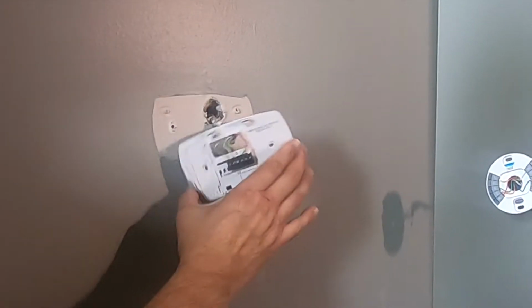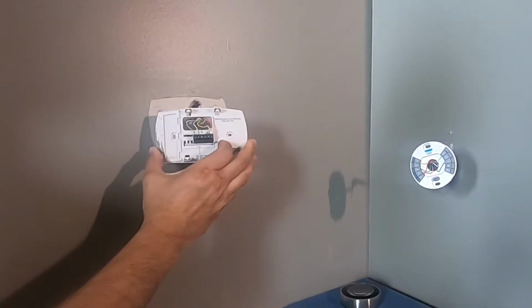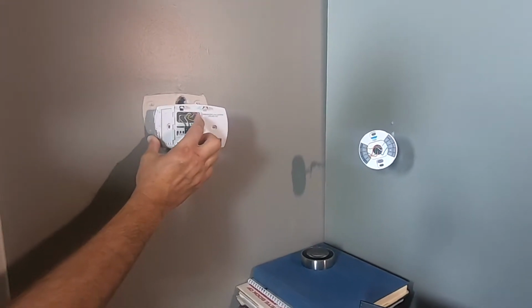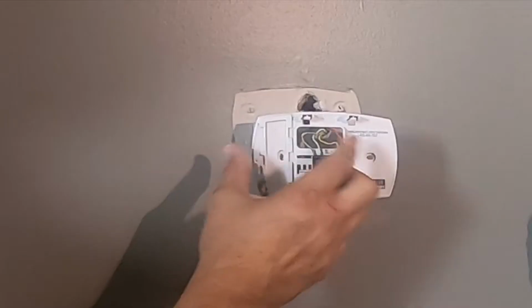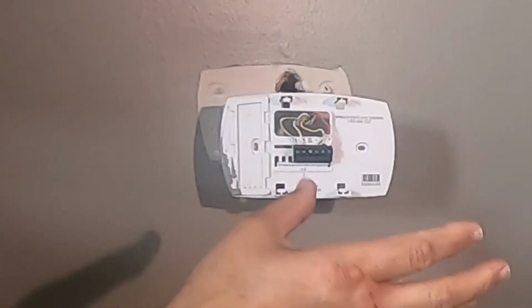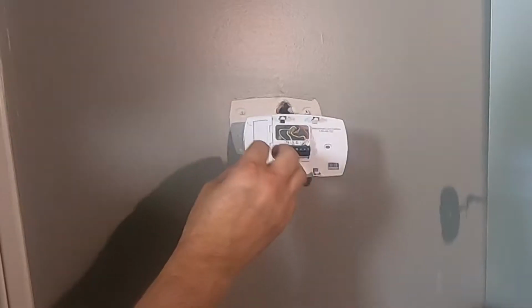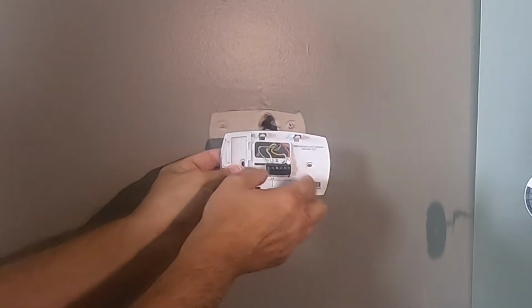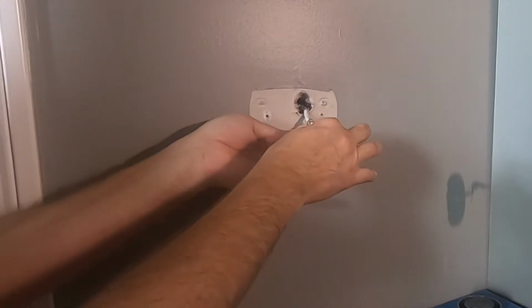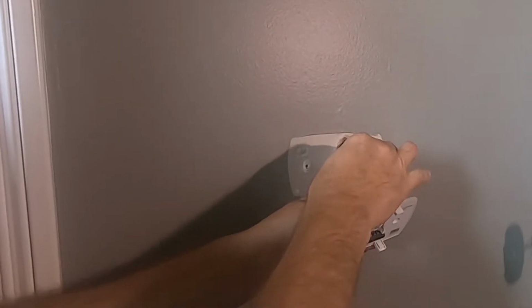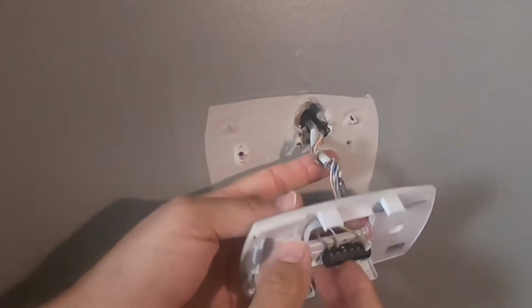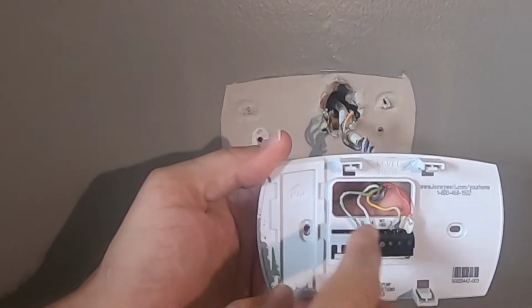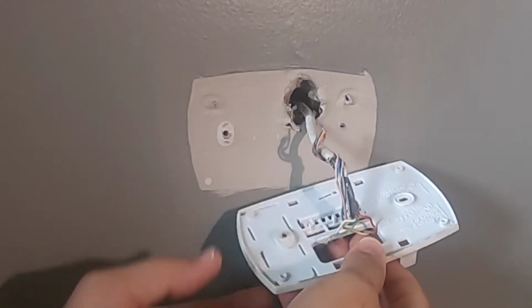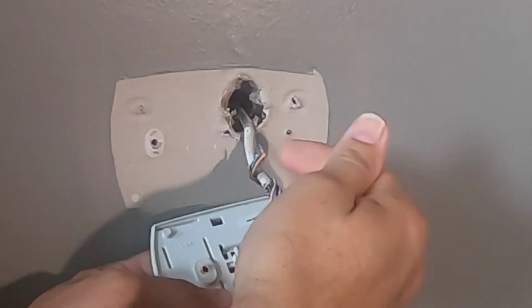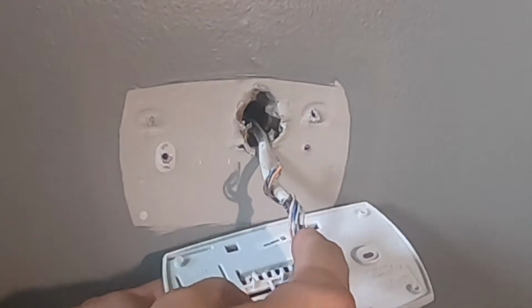Right here you can see this is our old thermostat mounting, and there are only four wires connected here. Each of these wires means something, and depending on your particular situation, there's a myriad of different ways. But what I wanted to show you is, even though there's only four wires connected here, there's a host of wires still on the back that are unused and unconnected. So if you pull off an old thermostat to put a Nest on there and you only see four wires, look behind it and see if you don't have extra wires that are unused on your old thermostat.